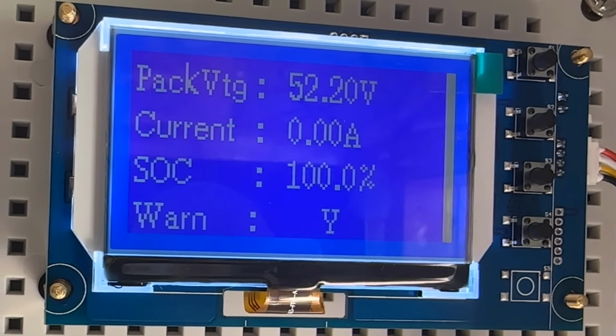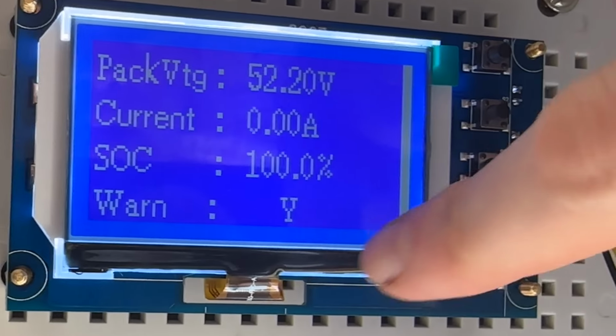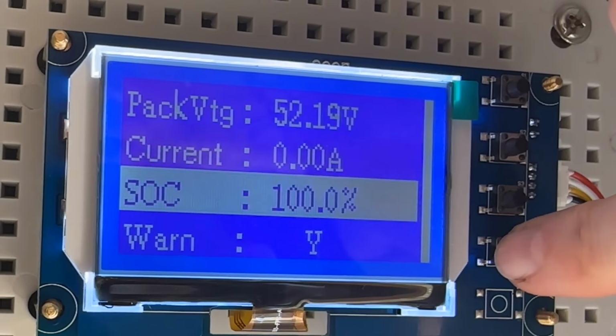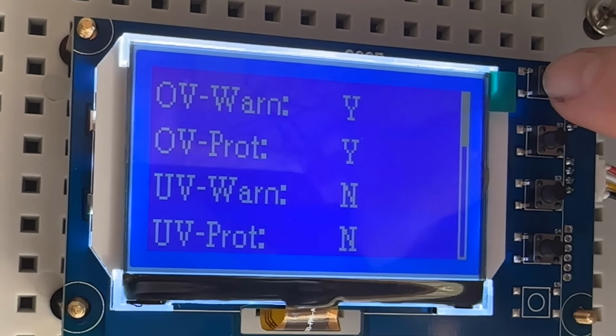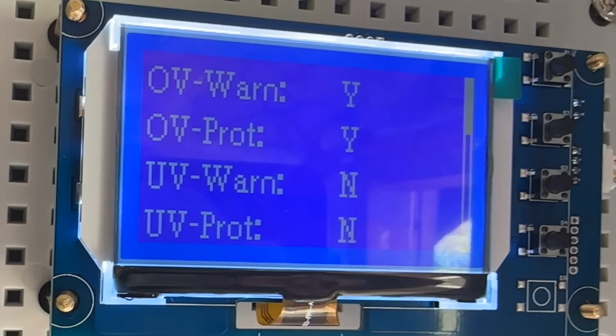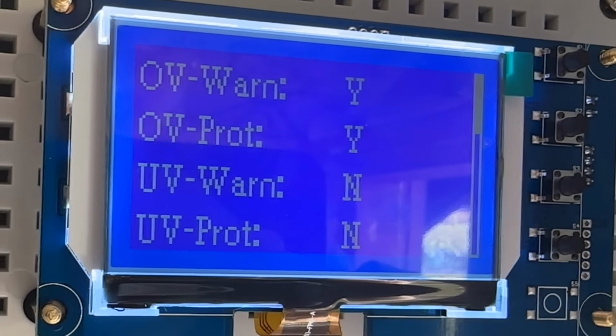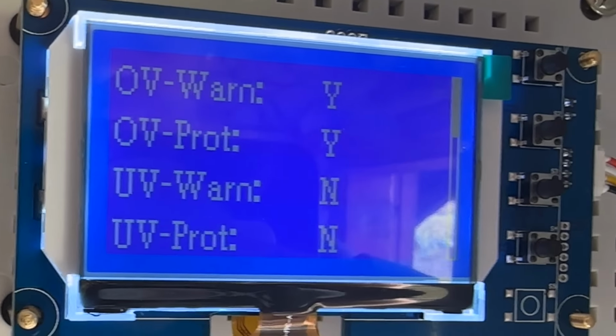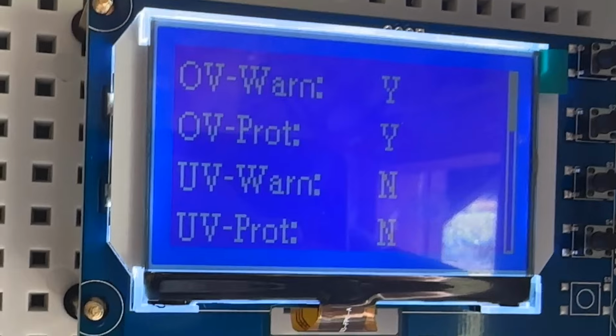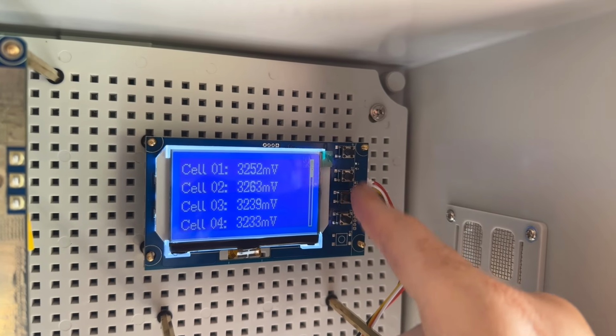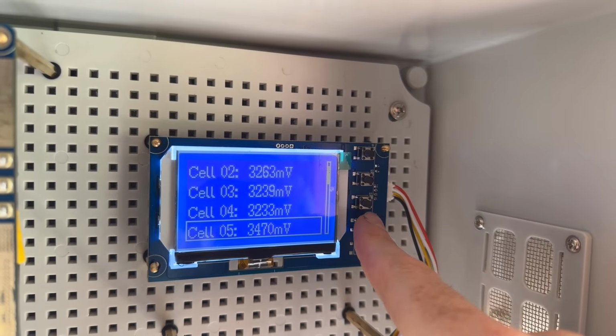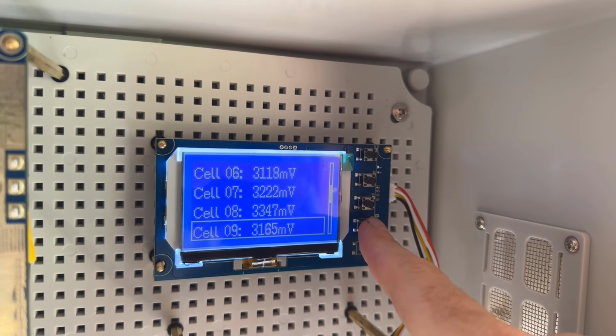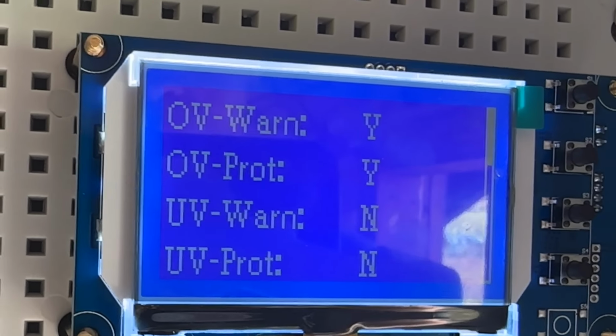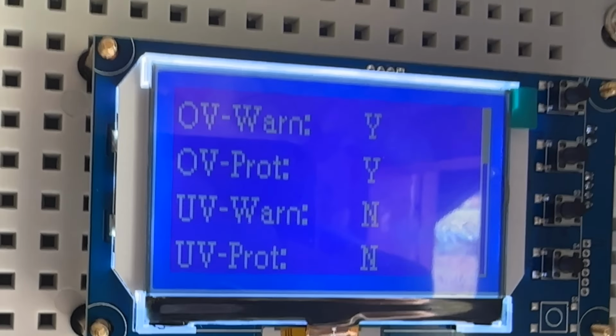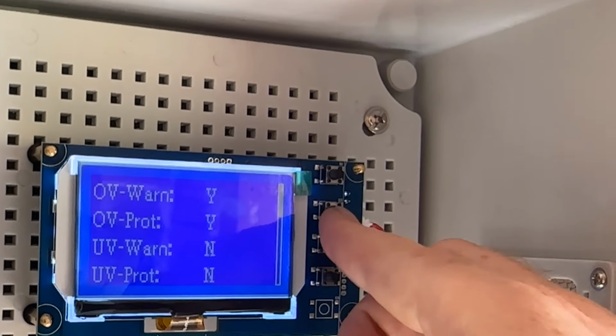We don't have the generator running anymore to have power, so that's great. We're pretty happy with this BMS so far. It does show a warning here - let's see - yeah, high voltage warning and high voltage protection. We did have a high cell fault, so it just triggered that and stopped it from charging. But it's pretty nice how this works. Let's see, where's the high cell? Yeah, cell 5 hit a high cell fault or high cell warning. We have solar available and it will charge once it's ready, and the Sol-Ark is listening to it, which is pretty incredible.